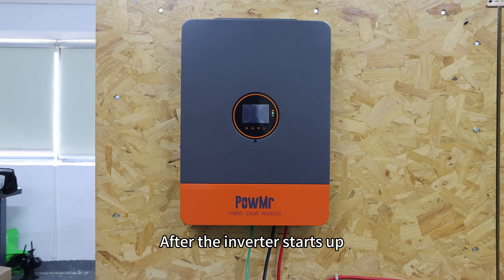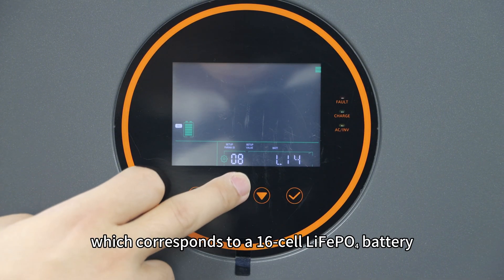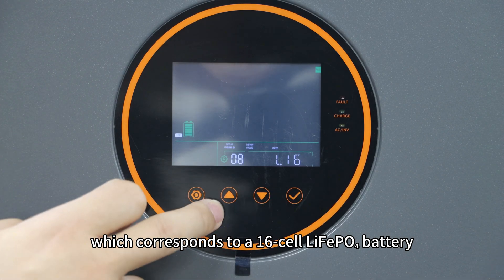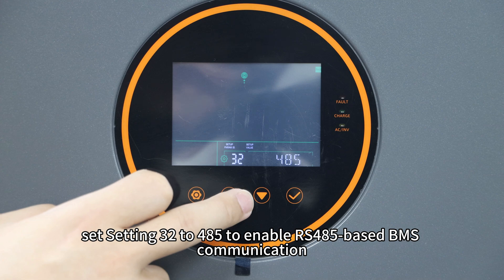After the inverter starts up, enter the settings menu. Set setting 08 to L16, which corresponds to a 16-cell lithium iron phosphate battery. Then set setting 32 to 485 to enable RS-485-based BMS communication.